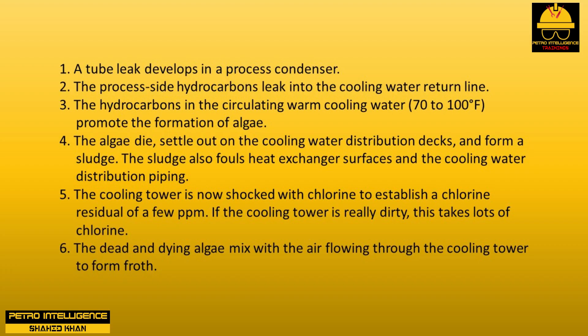Perhaps you have driven past a refinery cooling tower with frothy white foam billowing from its top. That's caused by the following sequence of events: one, a tube leak develops in a process condenser; two, the process side hydrocarbons leak into the cooling water return line; three, the hydrocarbons in the circulating warm cooling water — 70 to 100 degrees Fahrenheit — promote the formation of algae.